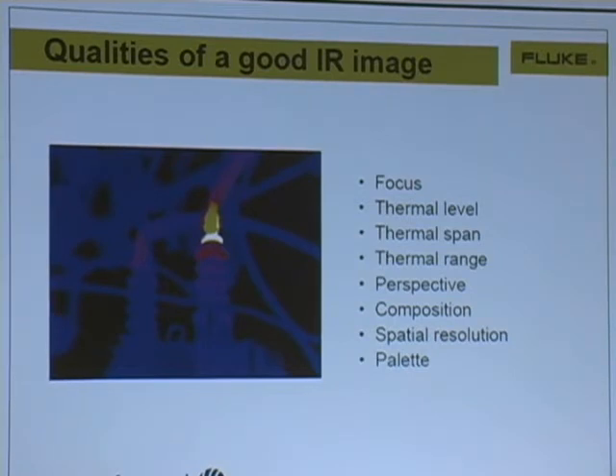Now let's get into temperature. You notice there's no temperature on this picture, for good reason. When you take pictures with a camera, it's kind of like taking it with a thermometer. Every thermometer is going to be a little different. Only it's a little more complicated because you can adjust this camera, you can't adjust the thermometer. You can be completely off with this thing. Remember I told you there's reflectivity, emissivity, and transmissivity? You can adjust all three of those things with this camera. You can tell it that something has a property that it doesn't. So the temperature is rather unimportant because of that.